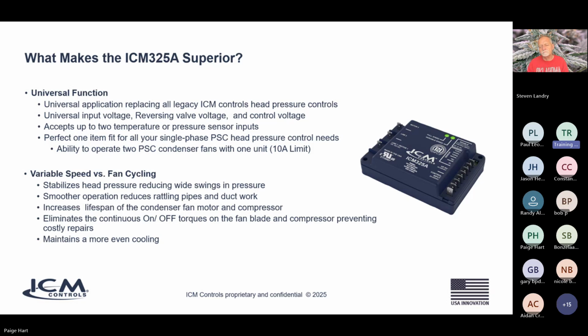Some people have even used these, and when they've got coils that have several loops in the coil, they can put one sensor on one loop and one sensor on another loop, and they can get better head pressure control that way as well. So it's a perfect one item fits all for your single phase PSC head pressure control needs.